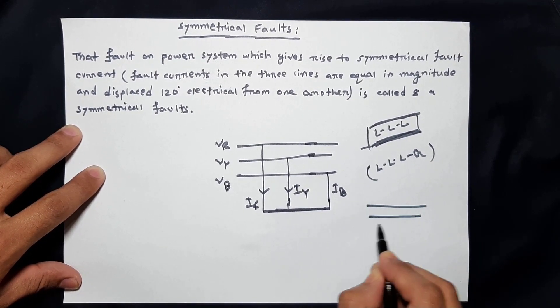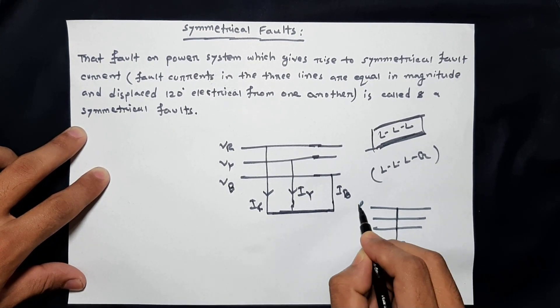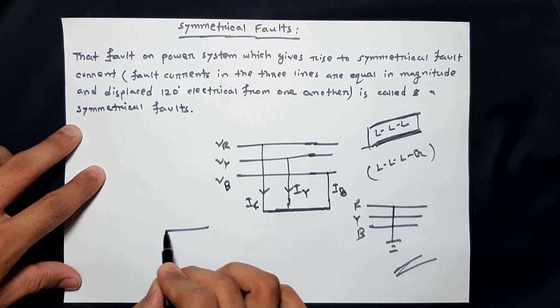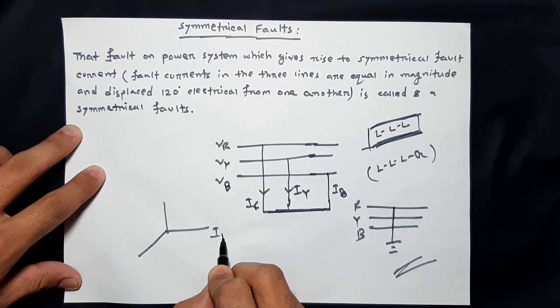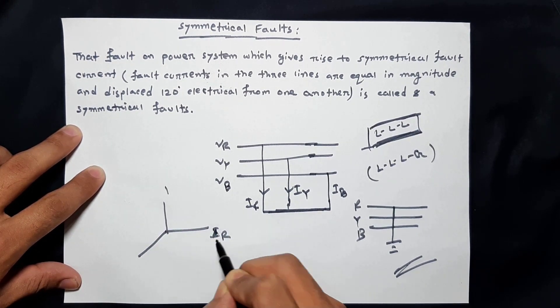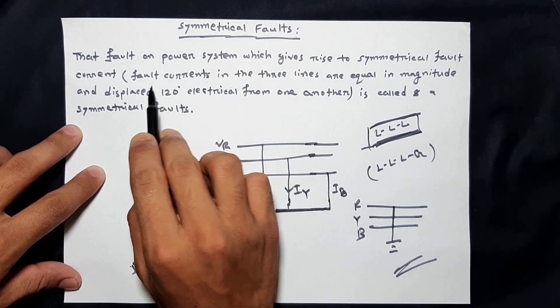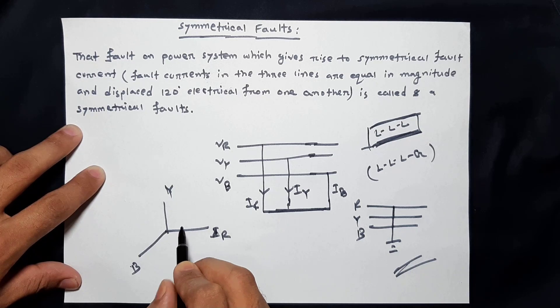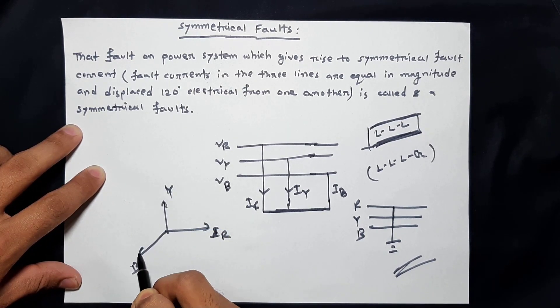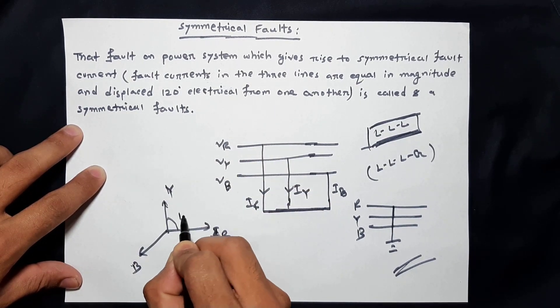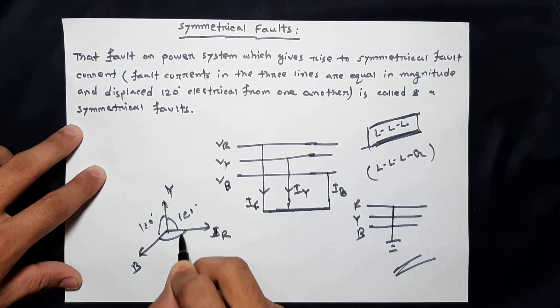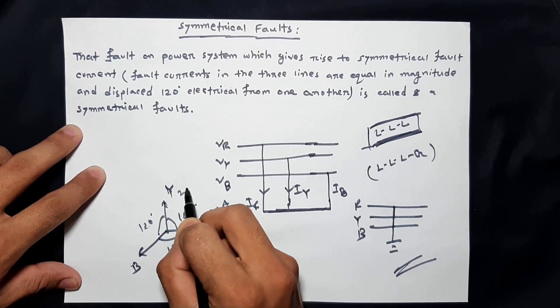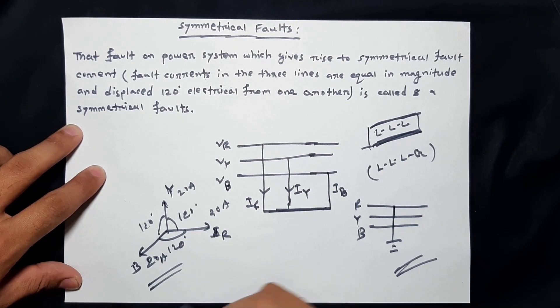When a symmetrical fault occurs, the fault current in the three lines — red, yellow, and blue — are equal in magnitude. That means the magnitude of fault current in all three lines will be the same. Additionally, the currents are displaced by 120 degrees electrically from each other — 120 degrees between each phase — making them symmetrical. For example, suppose in the red phase, 20 amperes of fault current flows; in the blue phase, 20 amperes; and in the yellow phase, 20 amperes — so the current is the same in all three. This is the concept of symmetrical fault current.